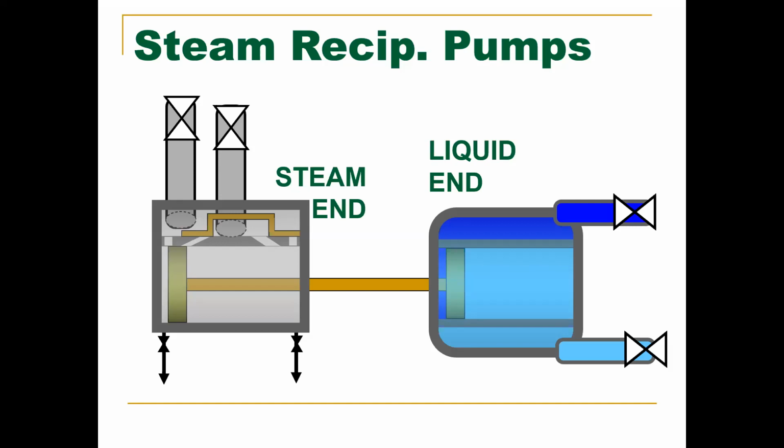If the system is not primed, you're going to open all valves in the system besides your discharge. You're going to open up your vent. Once you have flow coming out of your vent, you'll secure the vent. You will start the pump. You will then open your discharge valve slowly. The tank will fill. Once the tank is filled, you will close your discharge valve. You will shut down the pump, and then you're going to close all other valves in the lineup.